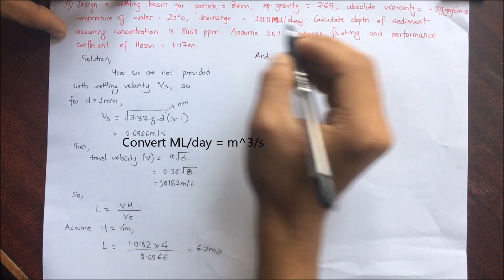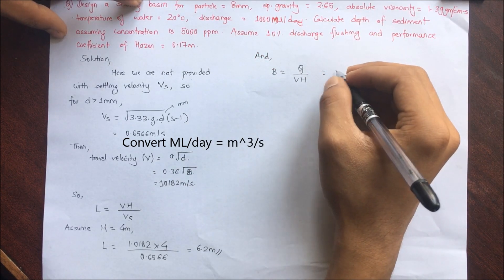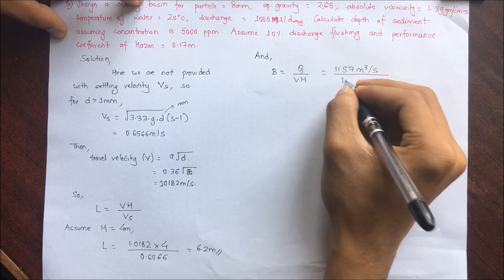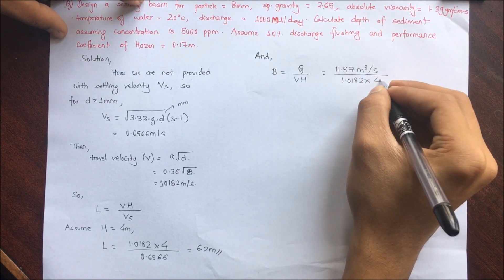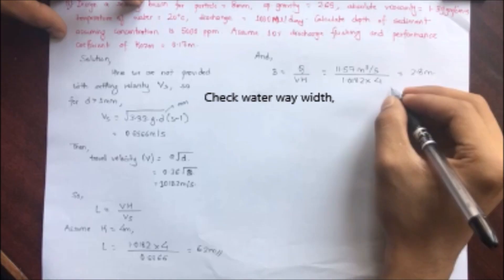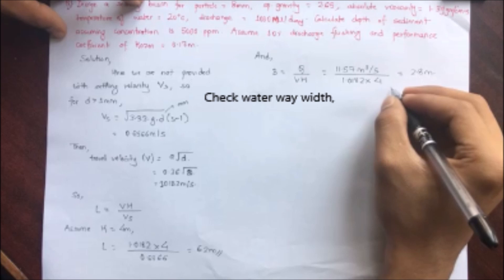Width B = Q / (v × H). Converting Q = 1000 million liters per day to m³/s gives 11.57 m³/s. So B = 11.57 / (1.0182 × 4) = 2.8 m. We also check this against B' = 4.75 × √Q = 16.57 m. Since we take the smaller value, B = 2.8 m is the width of the settling basin.